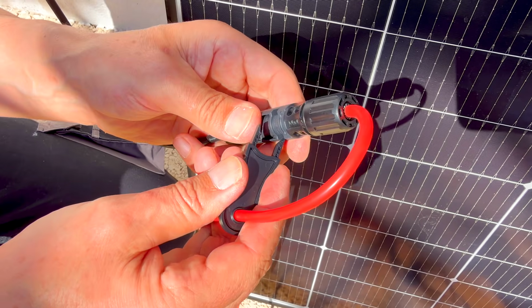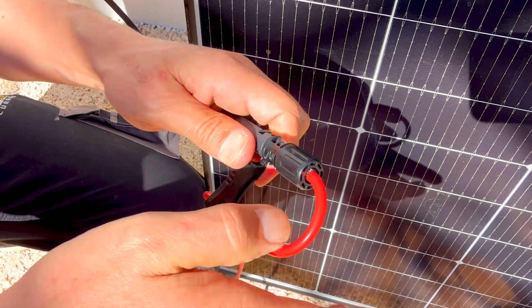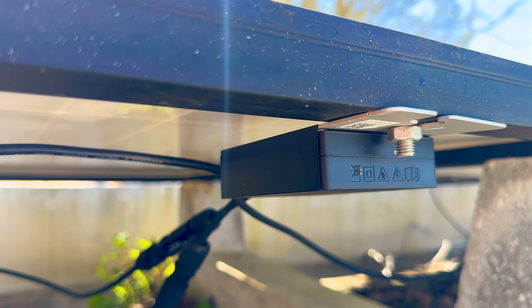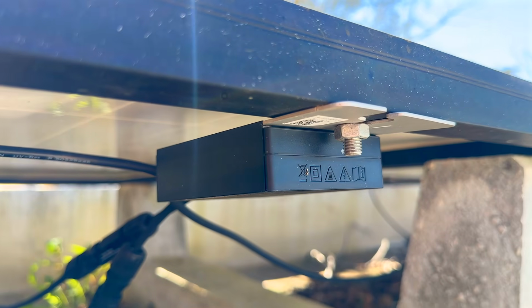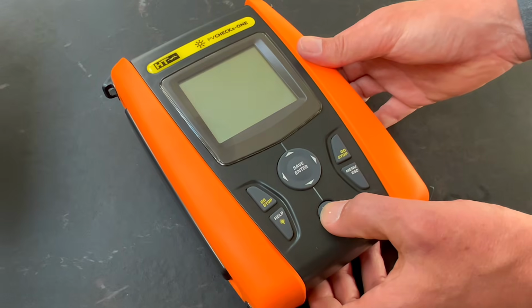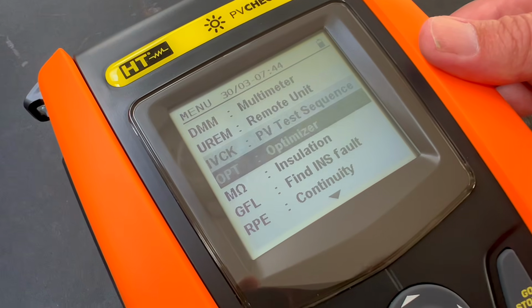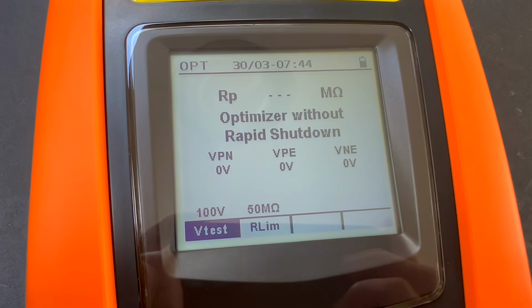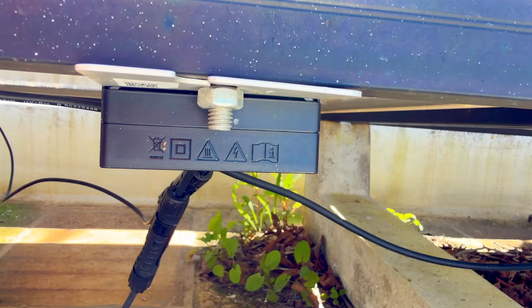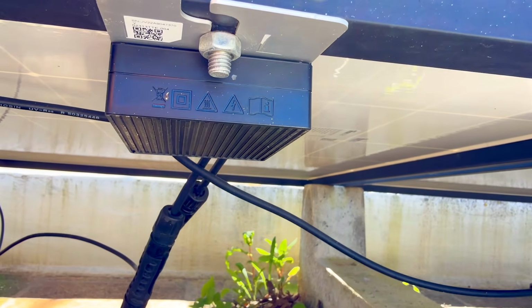Now, of course, if you are installing solar, there will be times when you need to do a little bit more accurate testing to ensure that the array is performing as intended in the design, which means you'll need a tester like the one we're going to look at on screen now that has a feature that's never been seen before when it comes to panels with optimizers installed.